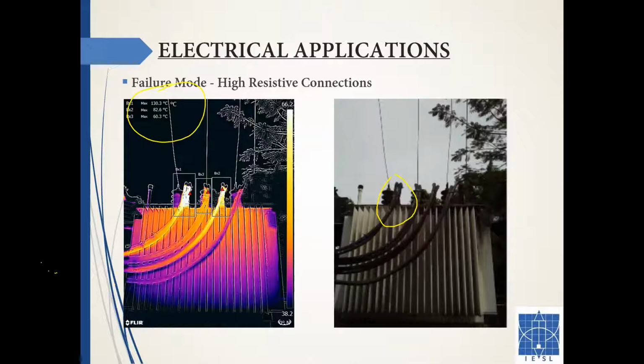To make sure, the best corrective action would be to remove the terminal and inspect it. It could be the lug, the terminal, the bolt, or the connection bolt. So remove it, inspect it, and reinstall it. Then what you need to do is take another image after letting it cool down.